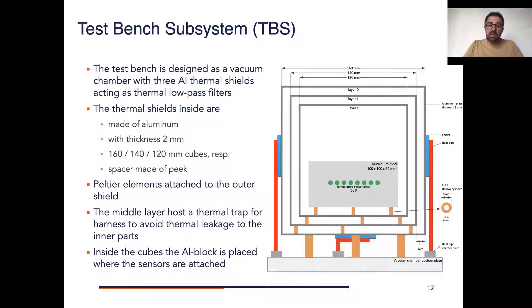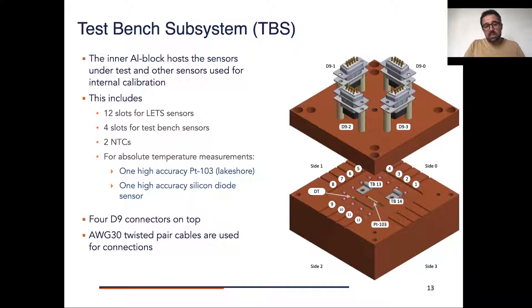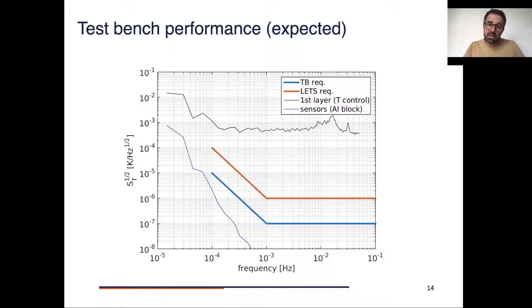On the inner part we have an aluminum block where we will attach our sensors. This inner aluminum block has the sensor under test, which we connect to our front-end outside, and also other sensors used for internal calibration. We have 12 slots for NTC sensors and other slots for high-accuracy platinum sensors or other technologies like silicon diode sensors, to do cross-check measurements during testing.